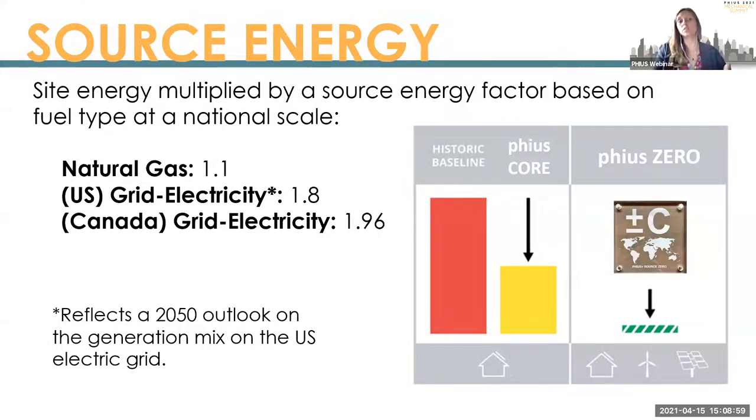the equipment that uses gas is not as efficient as electric equipment. So the theoretical maximum for equipment using gas is 100%. It's probably around 80 to 90. So you have to consider that efficiency in tandem with the source energy factor, where something using electricity can have an efficiency of 300, 350%. This is the coefficient of performance, the COP, which can be in the threes, maybe even up to four, often at least in the 200% efficiency.